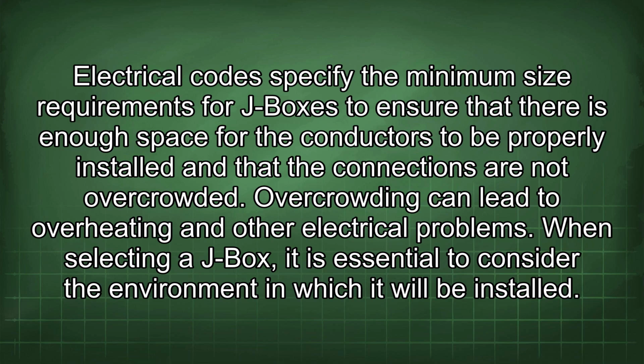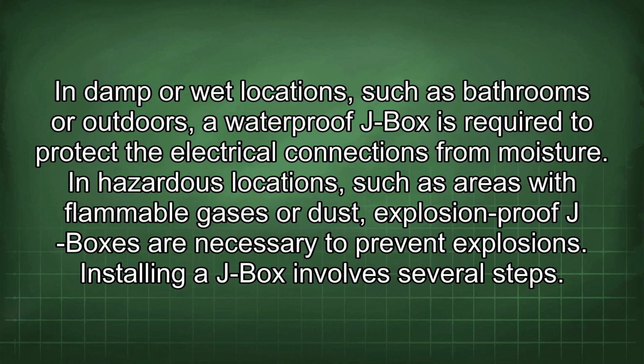When selecting a J-box, it is essential to consider the environment in which it will be installed. In damp or wet locations such as bathrooms or outdoors, a waterproof J-box is required to protect the electrical connections from moisture. In hazardous locations, such as areas with flammable gases or dust, explosion-proof J-boxes are necessary to prevent explosions.